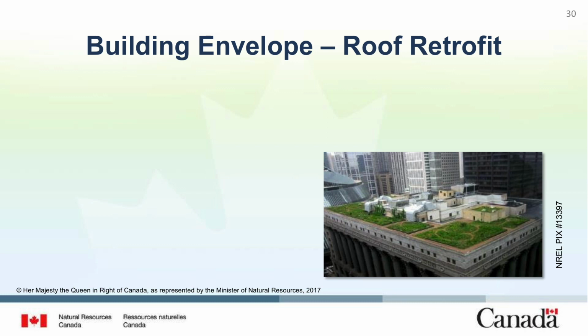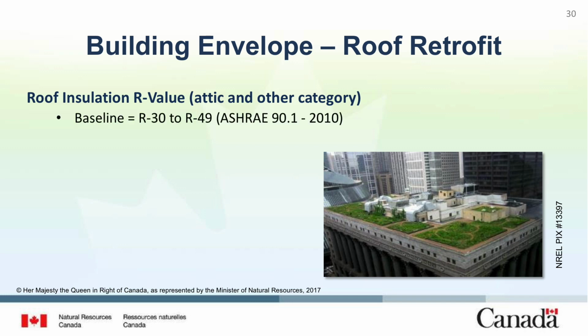When you're doing a roof retrofit, there are a few starting points you can consider. One of those starting points is going to be set to a minimum R value based on ASHRAE standard 90.1 and a target R value. As you can see, there are very aggressive insulation requirements. Reaching R50 to R60 would require a lot of insulation in the roof, either as an exterior foam board or an interior insulation. So you should use this target as a starting point and fine-tune this number based on any limitations you have with your existing building construction or the building location.